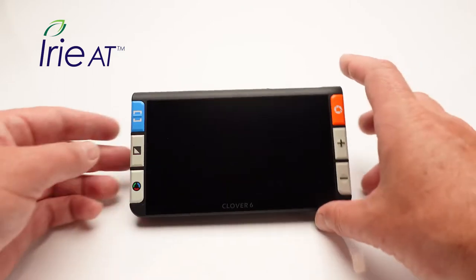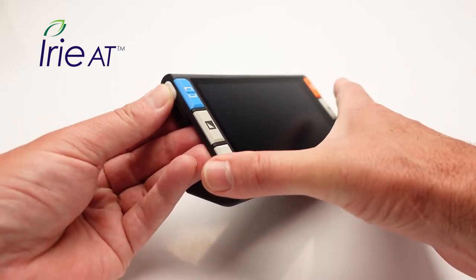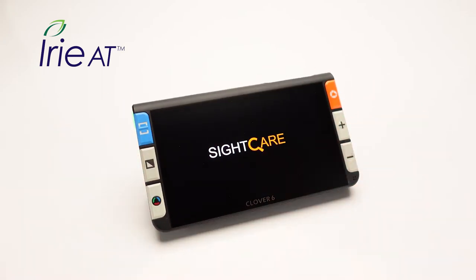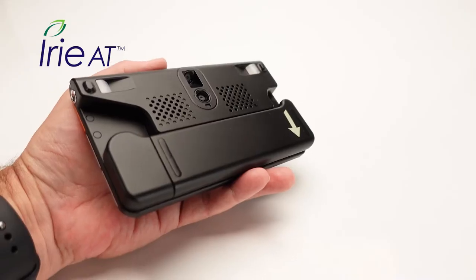There are a couple of ways to turn on the device. One is to press the power button on the top left side — just hold that down for a couple of seconds. It'll turn green, give you a vibration, and then the device will come on. You'll see the SightCare splash screen, the Clover 6 splash screen, then the LED lights come on and the device will be ready to use. You can also turn on the Clover 6 just by pulling down the handle into the reading position.